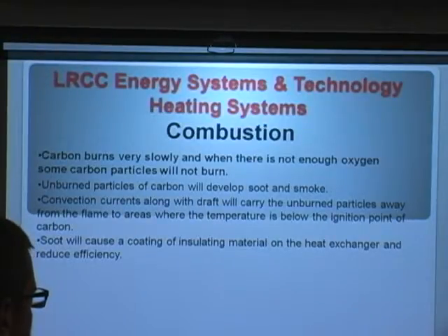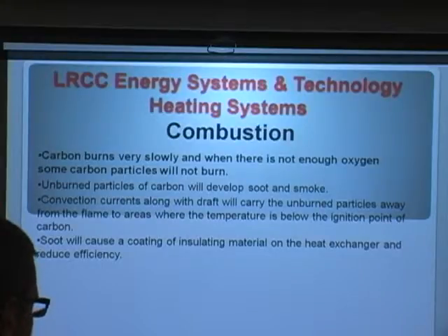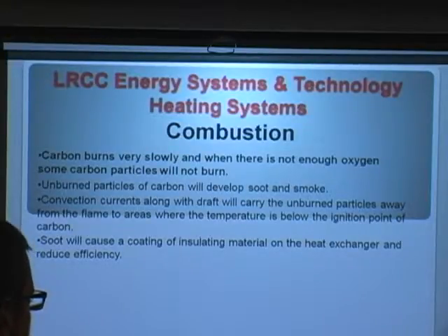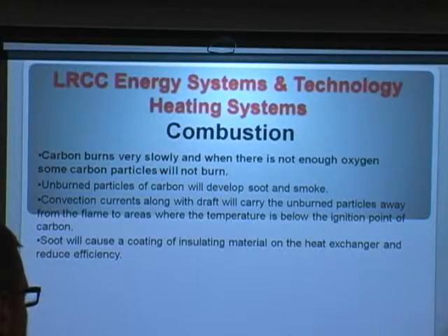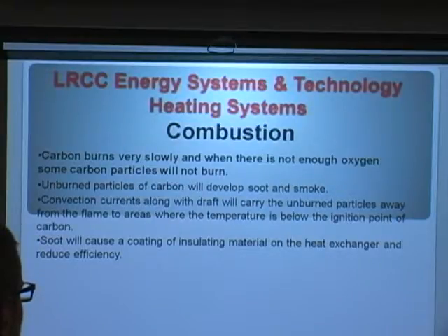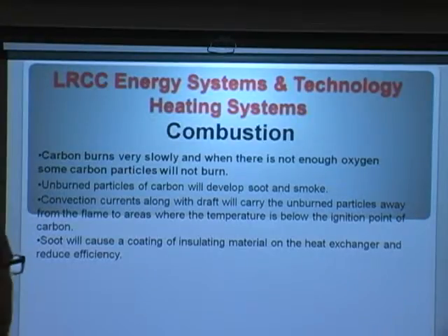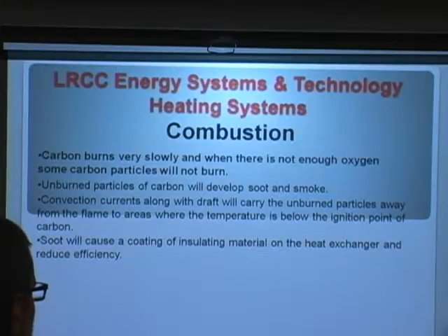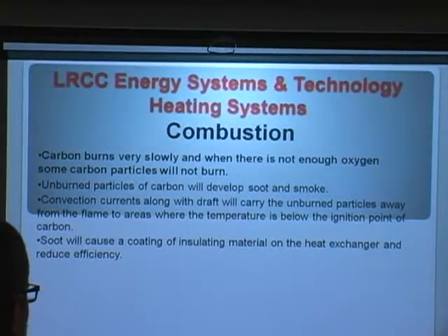This is where good maintenance comes into play. If the appliance has been running inefficiently for over a year and producing soot — what we call a sooted condition — and you come in and just adjust the flame to run more efficiently but don't get rid of the soot, you haven't gained much. You've got to clean the soot out to gain maximum efficiency. Service technicians first take the thing apart, take their brushes out, brush down the inside and vacuum it all out, getting all the soot off the heat exchanger. Once cleaned up, then they adjust the flame and get it running properly.